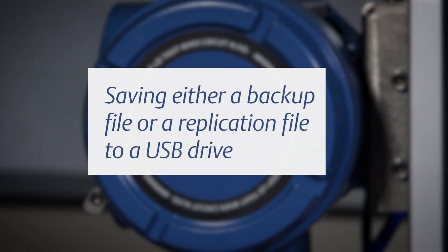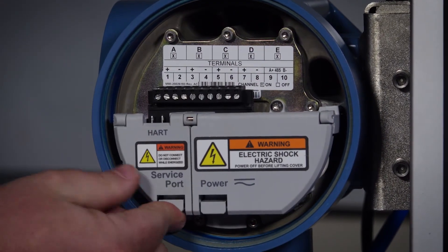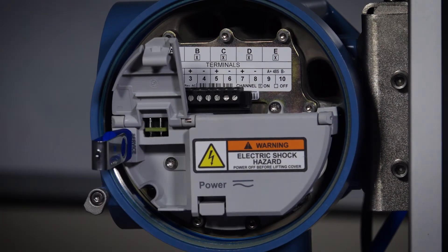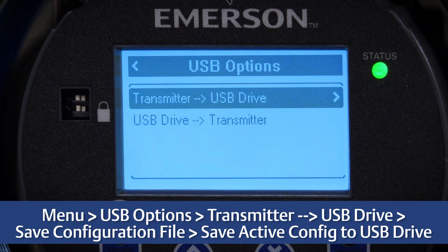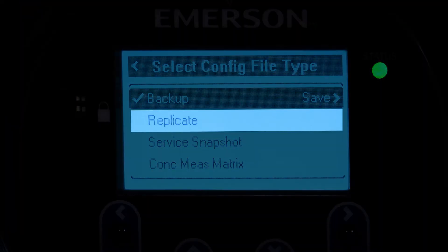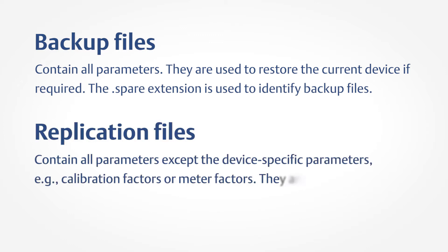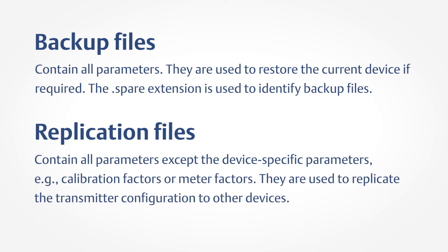To save the current configuration to a USB drive as either a backup file or a replication file, first open the wiring compartment on the transmitter and insert a USB drive into the service port. Choose Menu > USB Options > Transmitter > USB Drive > Save Configuration File > Save Active Config to USB Drive. Second, choose backup or replicate on the display screen. Backup files contain all parameters and are used to restore the current device if required; the spare extension is used to identify backup files. Replication files contain all parameters except device-specific parameters, such as calibration factors or meter factors, and are used to replicate the transmitter configuration to other devices.